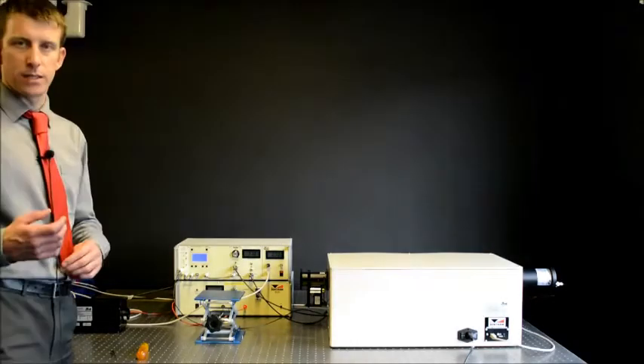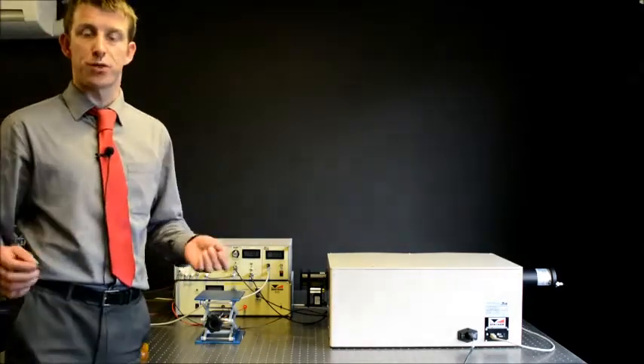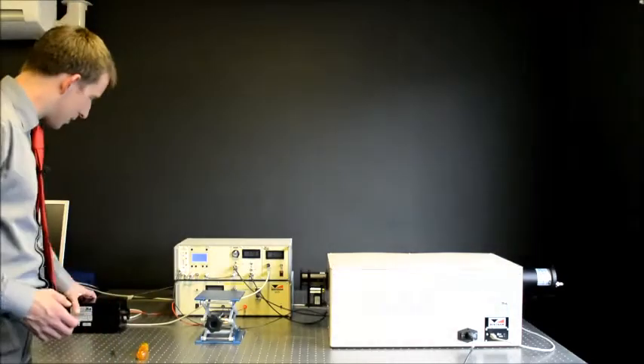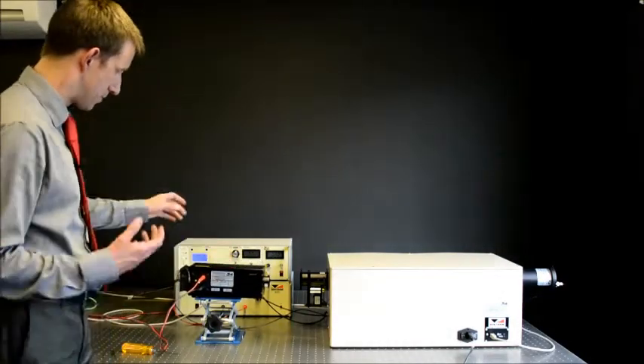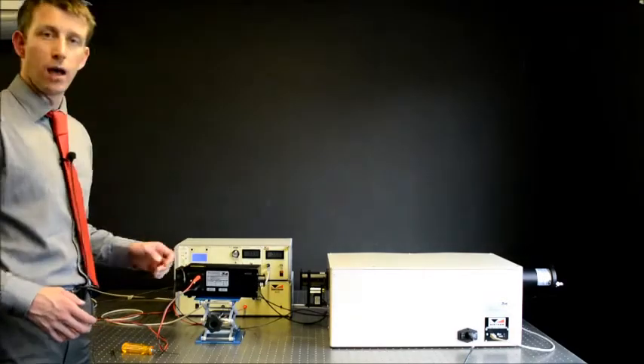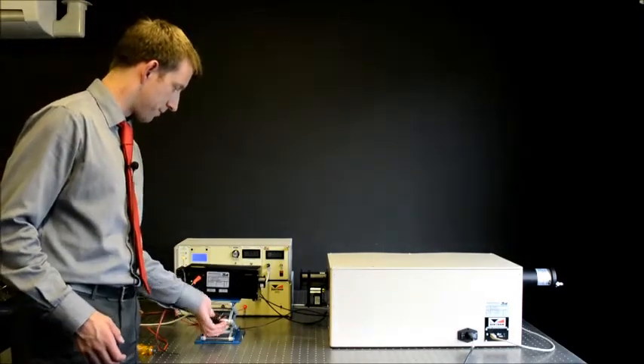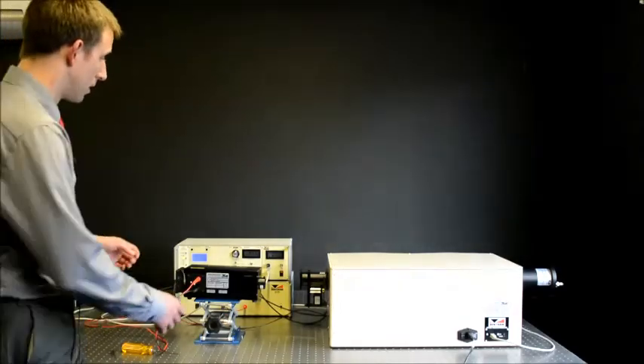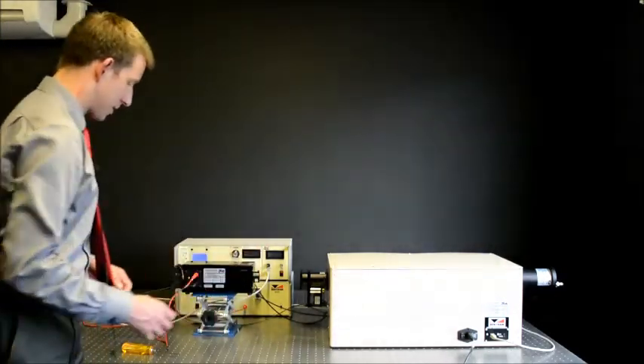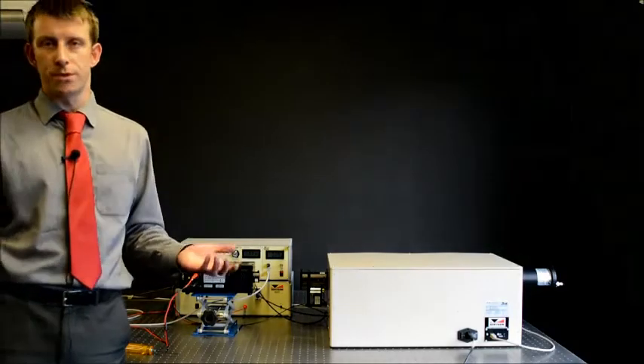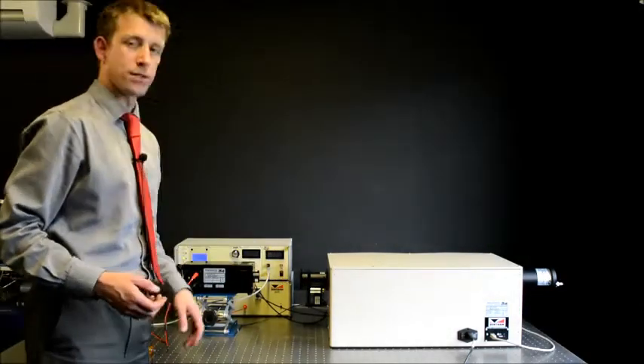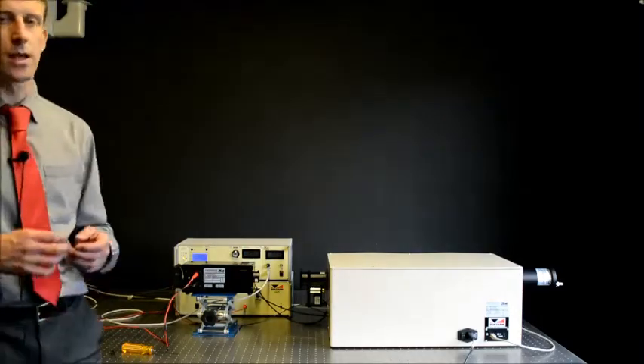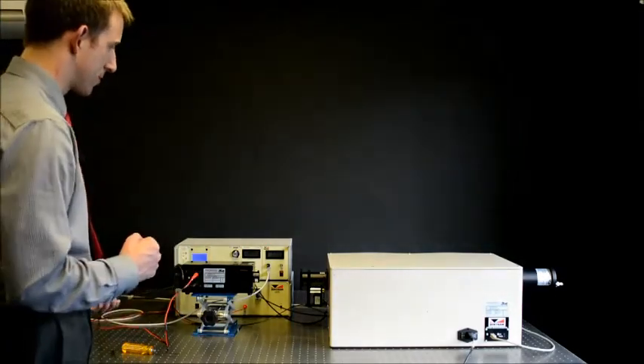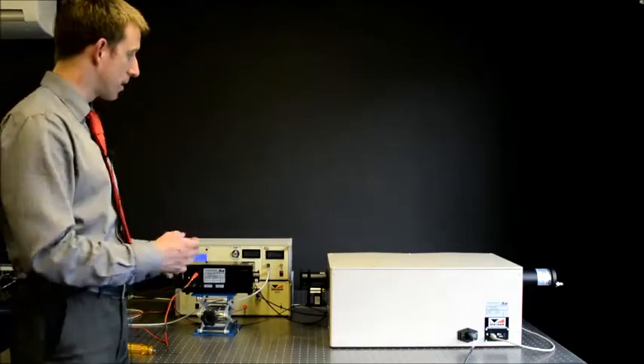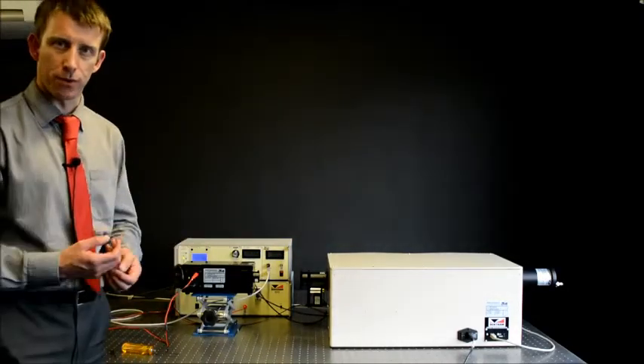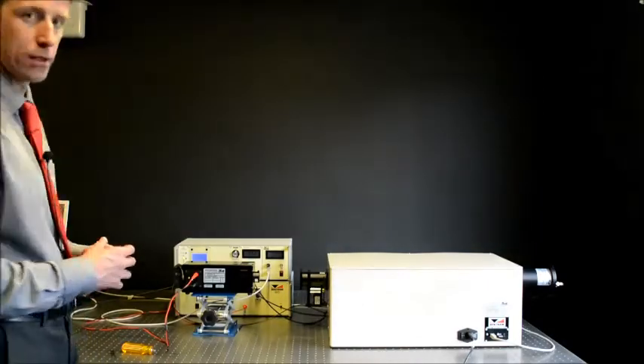We are measuring effectively, in this case, a relative spectrum in the infrared using the CL6 as the calibrant, which has been provided with a calibration up to 3000 nanometers. We need only position the CL6 at 200 millimeters from the front face of the relay optic. The distance is essentially not important, it's just some point of reference. This is a relative measurement. The more light we measure, the better, but clearly we cannot go too close to the relay optic, much like the spectral check measurement.